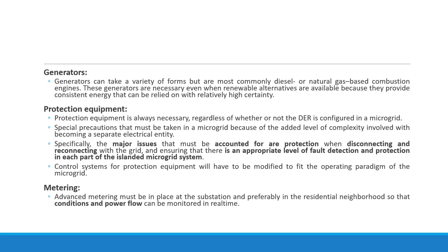The reason is that it provides consistent energy which can be relied on with relatively high certainty. Basically, renewables are uncertain. You cannot rely on them. But if a diesel generator set is there, you can be assured that there is consistent power, if the fuel is available, whether petrol or diesel. That's why, though renewable generators are there, at least a diesel or gas based generator should be available. It is not compulsory, but it is recommended that these generators should be part of the microgrid.